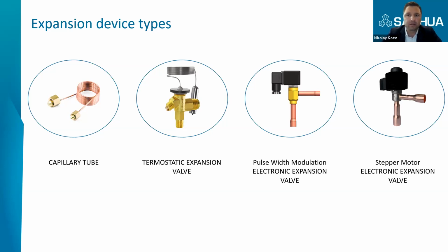The most sophisticated electronic expansion valve is actually the stepper motor valve. Here we have a stem, which is moved up and down by the motor of the valve. So the regulation of the refrigerant flow is very precise. Such valves have from 500 steps up to 5,000 or even 6,000 steps. So they're regulated very precisely by the controller.